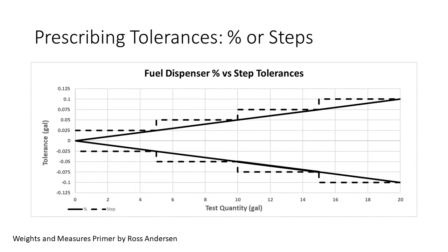This assumes that the instrument error will not invade the spaces under the step risers. The instrument must maintain 0.5% accuracy at all deliveries following the solid line. It does this by ensuring the scale divisions D are uniform in size pursuant to General Code G-S.5.2.3. This is a common way to graph error.